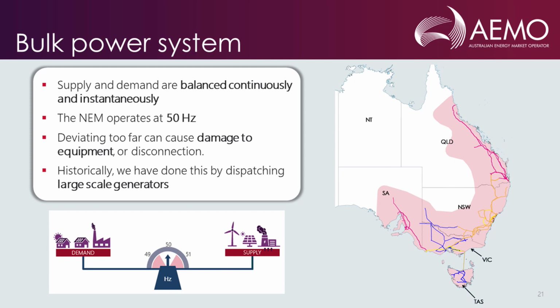This includes regulation FCAS, which is a correction of the supply-demand balance in response to minor deviations, or contingency FCAS, where for more major disturbances, such as a sudden loss of a generating unit, major industrial load, or a large transmission element that results in a noticeable frequency deviation, rapid injection or removal of electricity is used to correct the imbalance. This can be achieved through generator governor responses, load shedding, or rapid generation from a fast-starting generator.